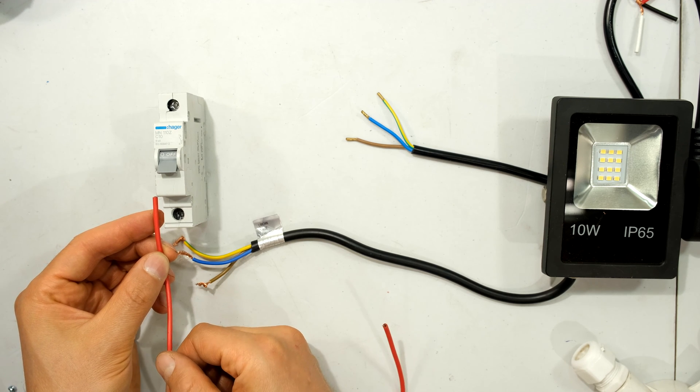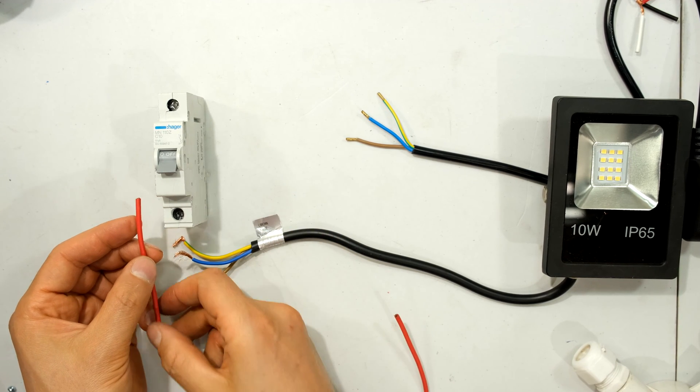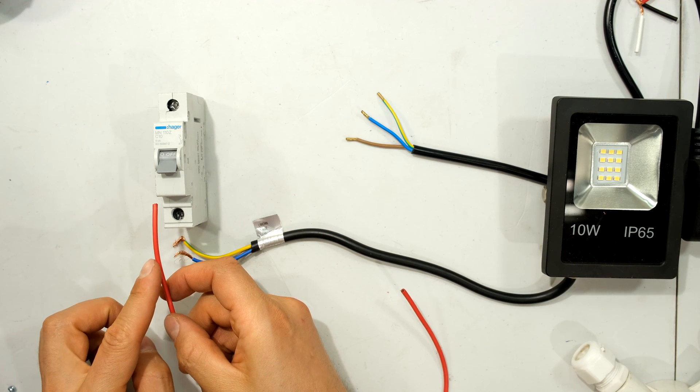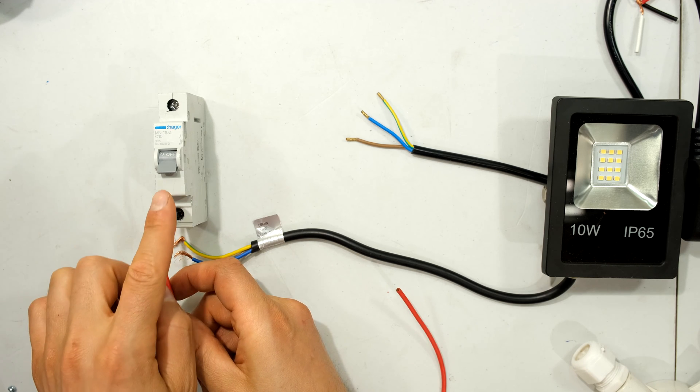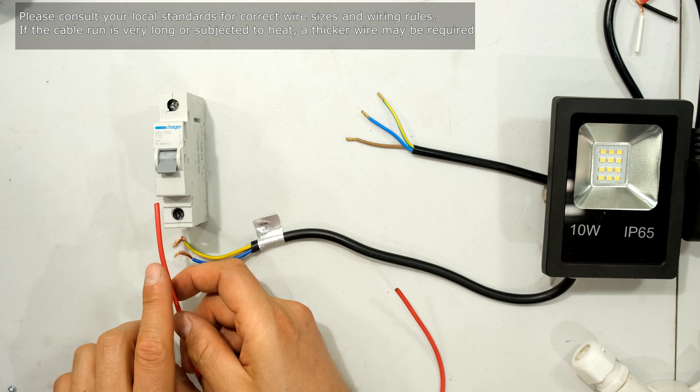There are specific rules about wire size for circuit breakers. I'm just giving a brief explanation that the wire must be able to handle higher current than the circuit breaker. The reason being is that the circuit breaker must trip before the wire burns.